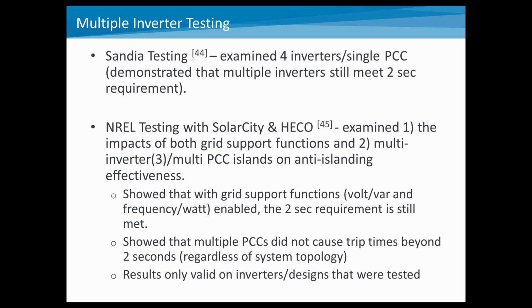But the results show that with grid support functions enabled, so volt-var control and frequency-watt enabled, the two-second requirement was still able to be met. It also showed that multiple PCCs did not cause trip times beyond two seconds, regardless of system topology. Again, this was scattering multiple inverters at multiple points of common coupling, and then doing the same type of unintentional islanding test on that much larger system. One thing we would point out from this result is that these results are only valid for the inverters and designs that were tested, but they do show that the popular designs that are out there do meet these types of requirements when looking at multiple inverters.